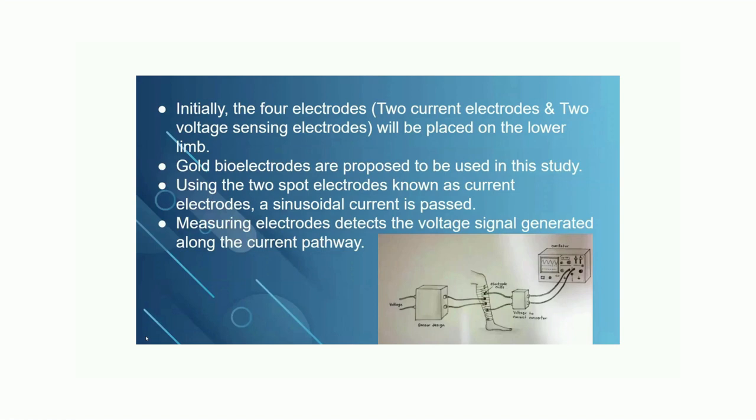The method of measuring process is as follows. Initially, the four electrodes will be placed on the lower limb. Two voltage electrodes will be surrounded by the two current electrodes. And we are expected to use gold bioelectrodes to ensure good conductivity and their low reactivity when in contact with human body. Then a sinusoidal current will be passed through the current electrodes and voltage difference will be measured. Then the blood volume flow will be measured using Nyboer's formula.